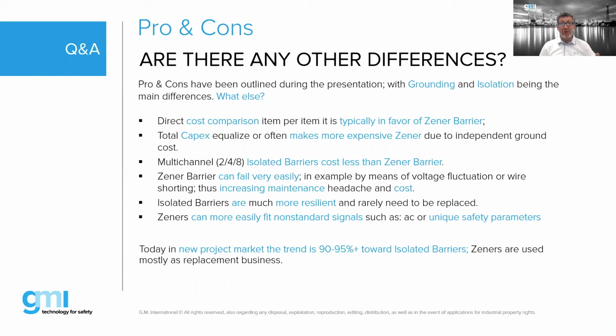With an isolated barrier, you can go as small as 6 mm, whereas Zener barriers are not so small, because internally the Zener diodes required to operate are very big. They're not the same Zener diodes used in an isolated barrier, because they have to withstand much bigger currents and voltages. So they're physically quite big. I believe there are 17 or 20 mm Zener barriers. And you also need two, or a double channel, which most people don't realize, because you need one barrier on one wire and one on the return wire, unless you want to ground the return wire. Right, that we haven't talked about much, but what else did we mention here?